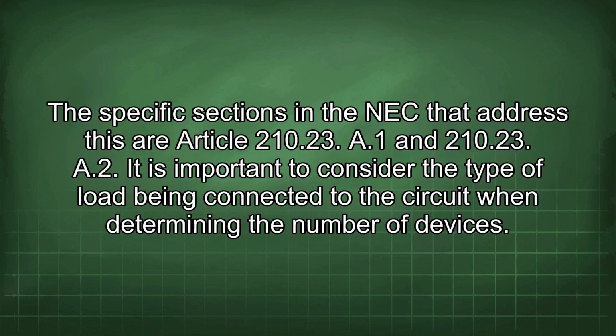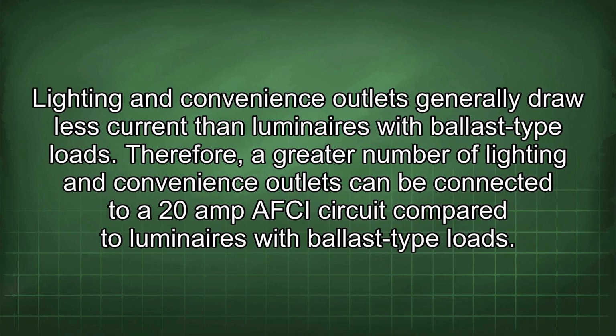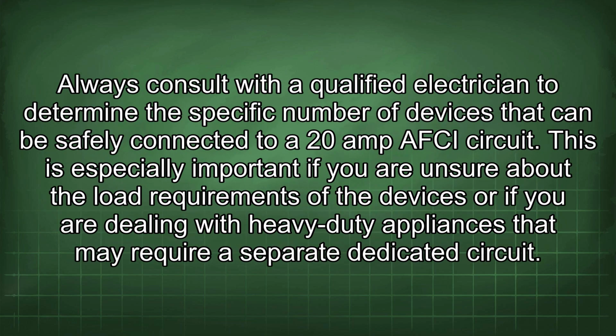The specific sections in the NEC that address this are Article 210.23, A1 and 210.23, A2. It is important to consider the type of load being connected to the circuit when determining the number of devices. Lighting and convenience outlets generally draw less current than luminaires with ballast-type loads. Therefore, a greater number of lighting and convenience outlets can be connected to a 20 amp AFCI circuit compared to luminaires with ballast-type loads. Always consult with a qualified electrician to determine the specific number of devices that can be safely connected to a 20 amp AFCI circuit.